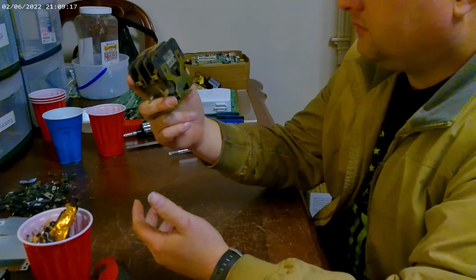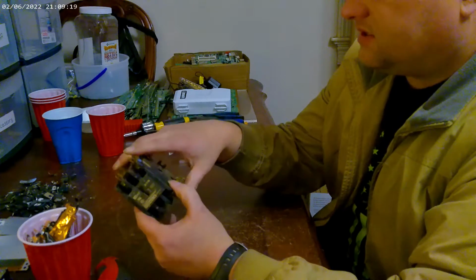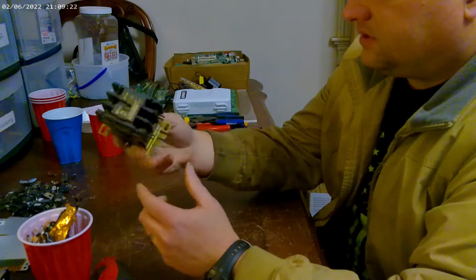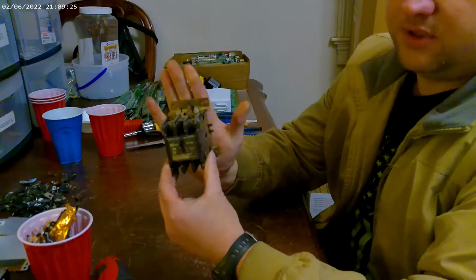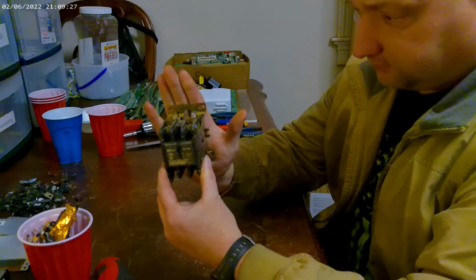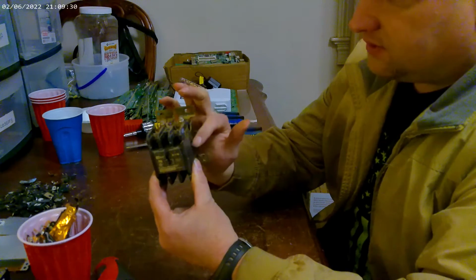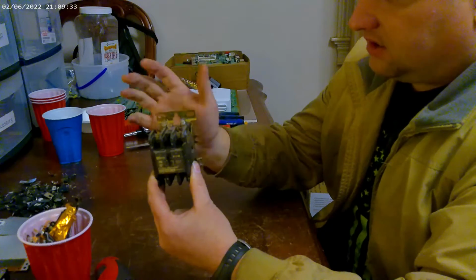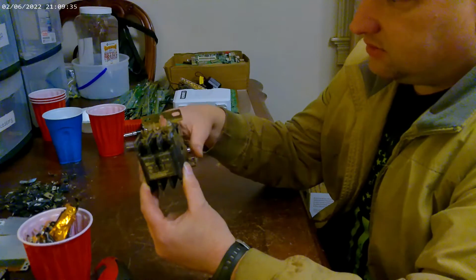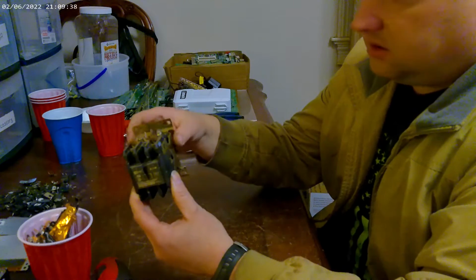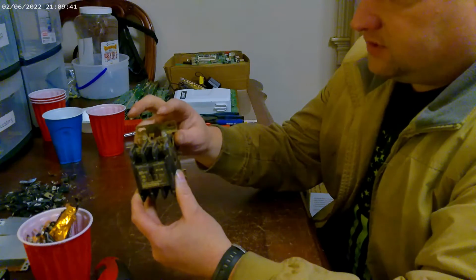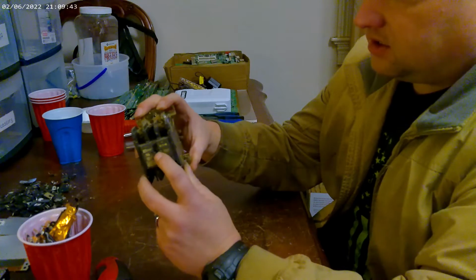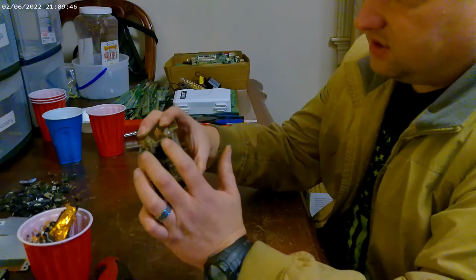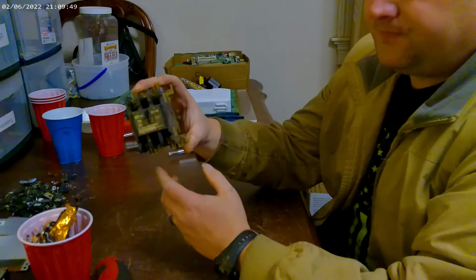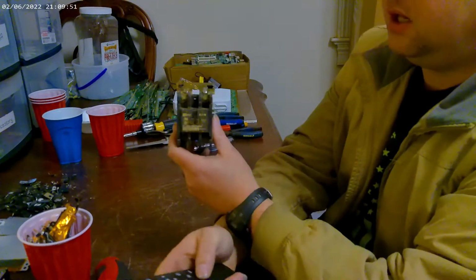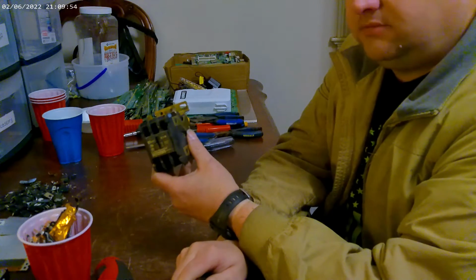So basically that's about it. Just to give you an idea of what these are. They're normally mounted on a wall or something like this inside of a panel. Those relays do go bad, so you can easily replace them by taking the screws out, pulling it out, putting another one in, and you're good to go. So again, low voltage side right here turns on the relay and closes, finishes that electricity through here to run whatever it is you want to run. So y'all hang tight, we'll be back with you in a second, and we will see what it looks like inside.